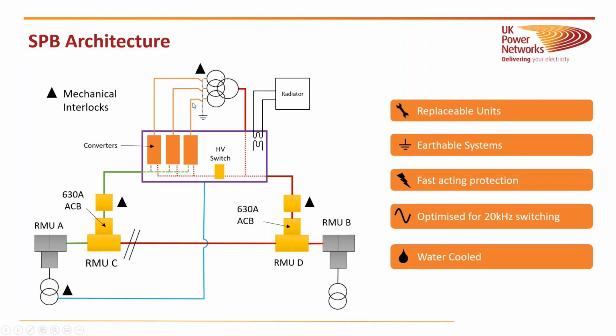I should probably point out that the way these converters work is they float on the voltage between each feeder. So they're essentially floating on the voltage, and therefore they're insulated from ground. They float at 1,000 volts, but it means they're not grounded in any way. So when you do need to maintain them and work on them, you need to make sure that somehow you can earth them to be safe.